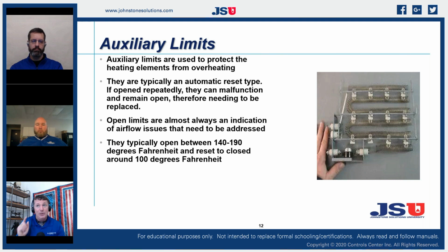But if we have a plugged filter on this electric furnace and that heating element is constantly at 150 degrees, let's open. Okay, let's let the blower run till we get down to 100 degrees. 100 degrees. Okay, let's close. We're ready to go again. And off we go. We warm up, get to 150 degrees. And oh, I've got to open up and cool back down again. That was supposed to be a safety switch. Now it has become a regulating device.